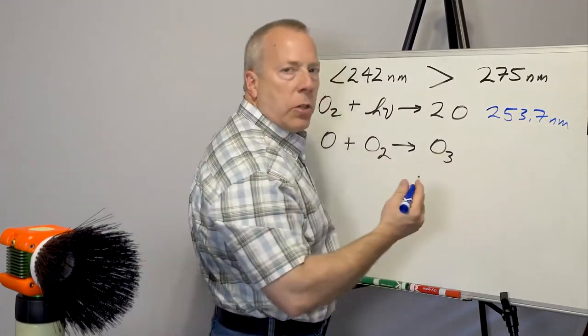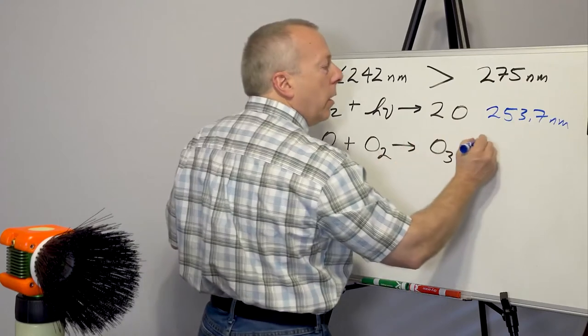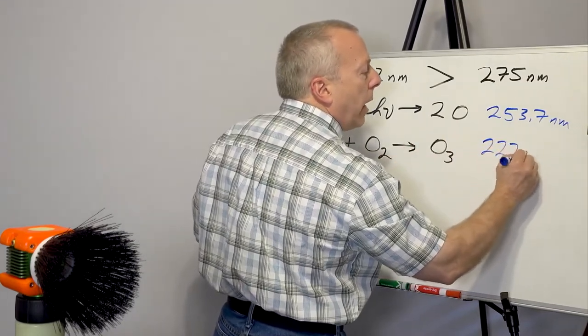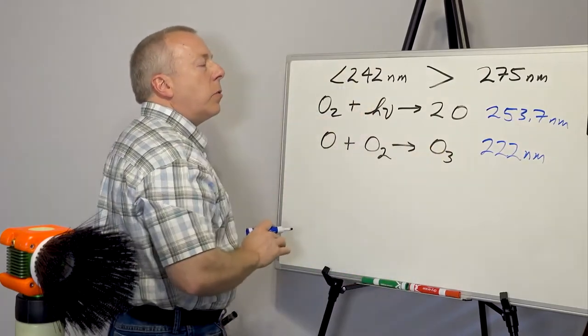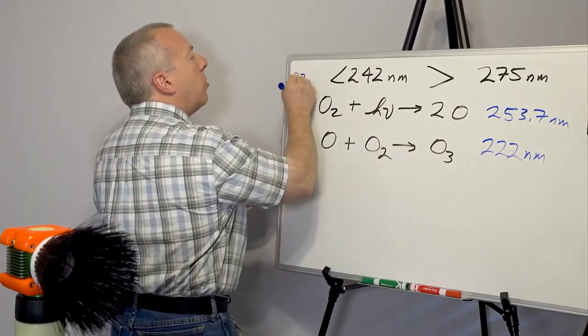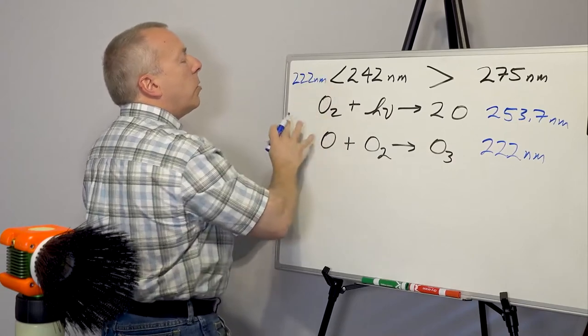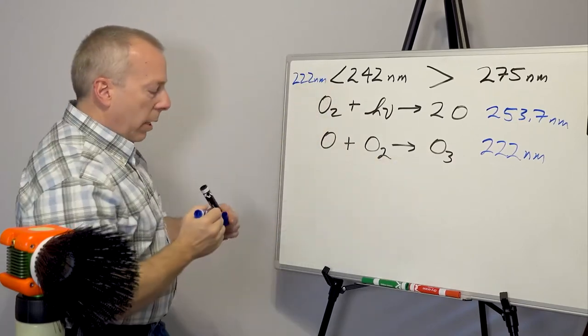However, the excimer system that's becoming more popular is at 222 nanometers. It is less than 242, so it's down here in this range at 222 nanometers. So it actually will generate the ozone.